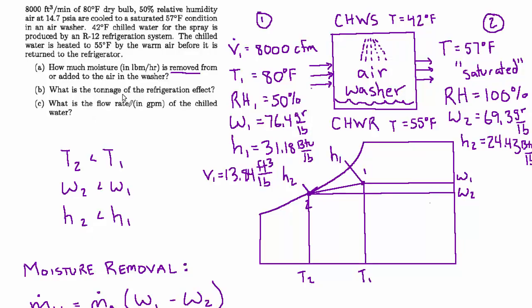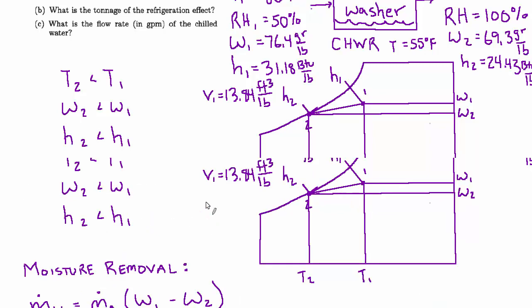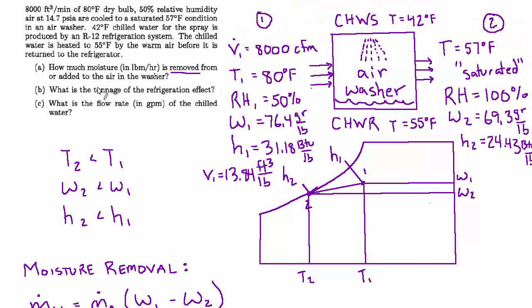Next, they wanted to know what's the tonnage of the refrigeration effect. So what we just dealt with in terms of change in the humidity ratio really only speaks to the latent cooling that's happened. Now they're asking the tonnage of the refrigeration effect, which includes in its entirety the net cooling. In this case, we had latent cooling and sensible cooling.